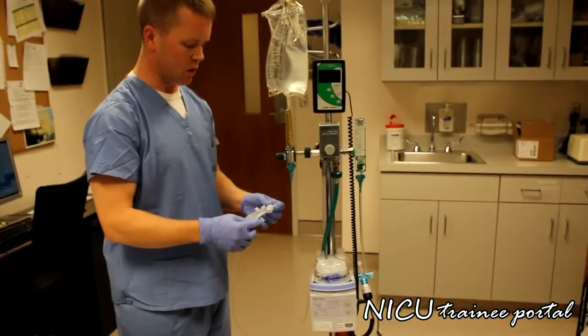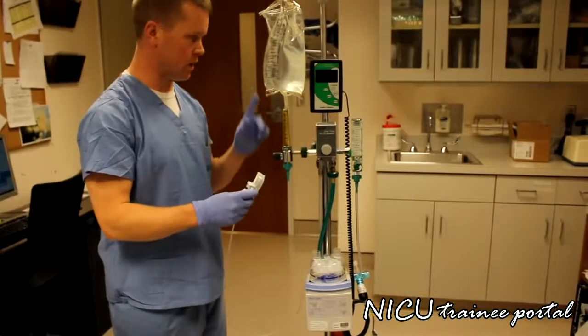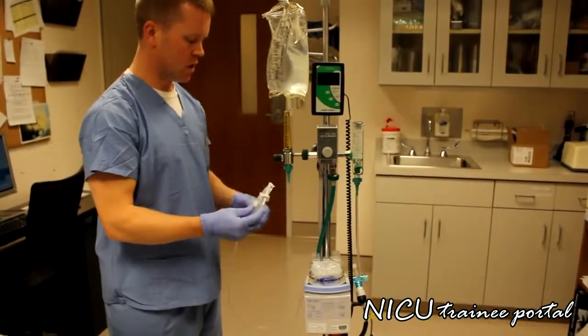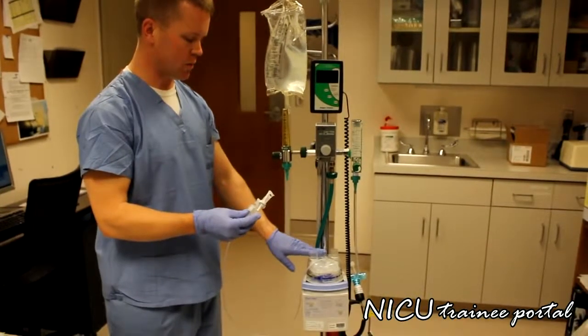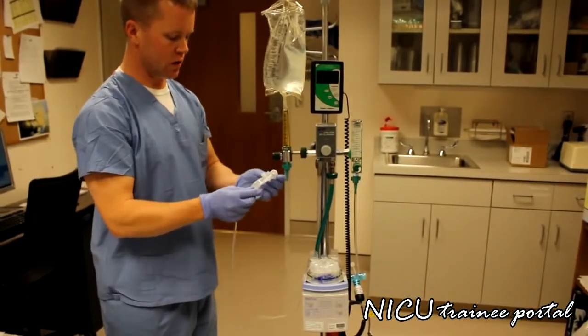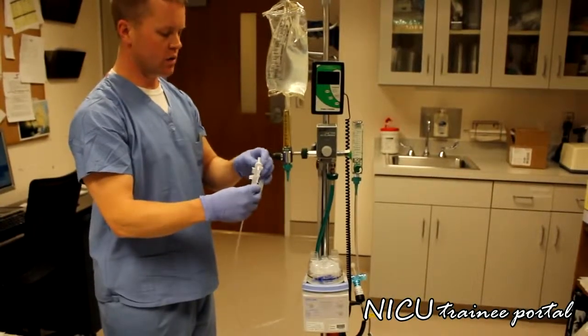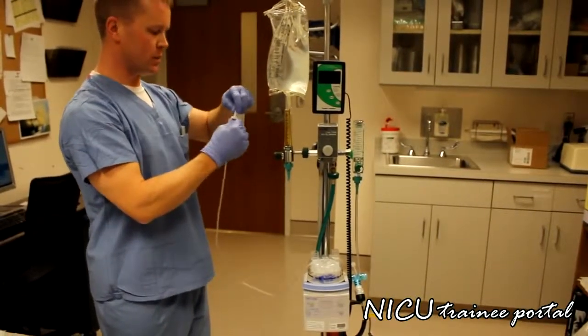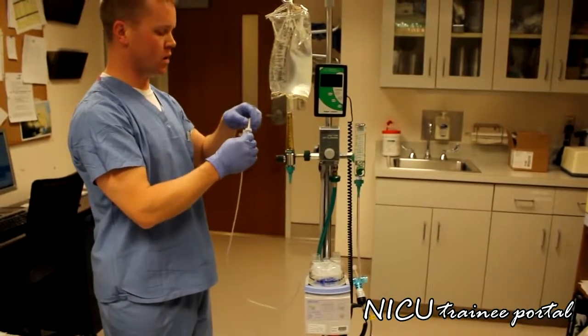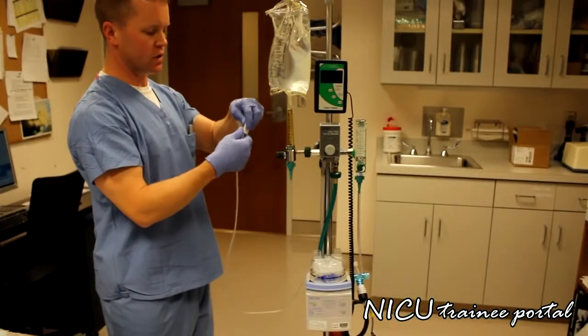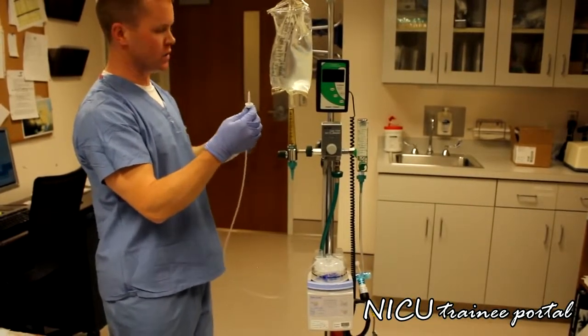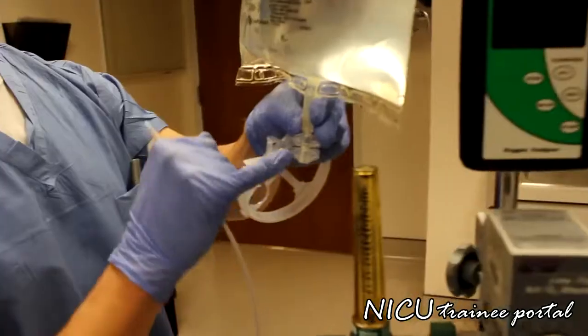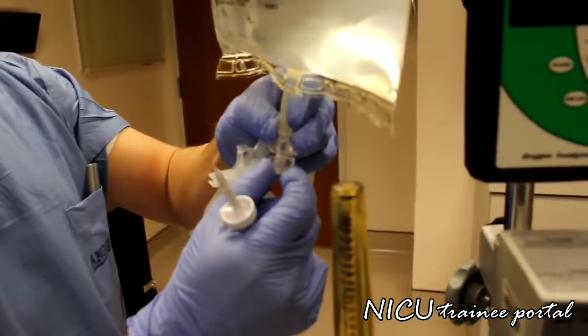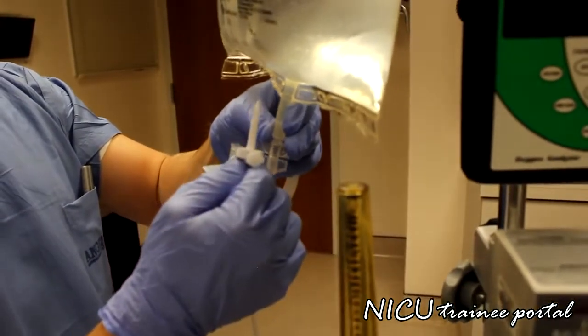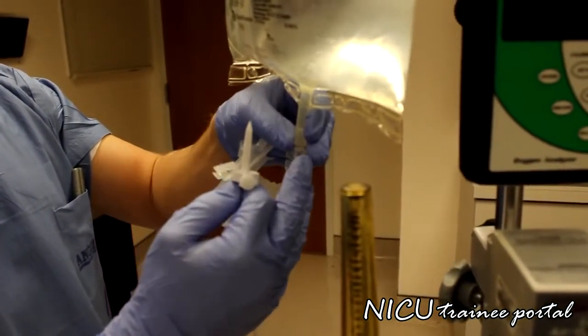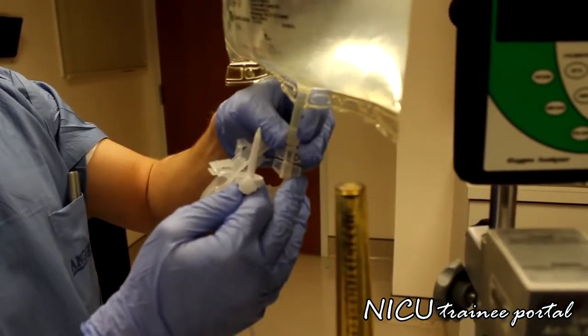Okay, the next component we will connect is the water line to the sterile bag of water for inhalation purposes. Attached to the heater to the water chamber is this water line. So it comes raveled around this piece right here. You unravel it, and for demonstration purposes, we will not be spiking this bag of water, but inside of this little plastic connection is a spike. And when you're ready to, you displace plastic on the bottom. This piece twists off. You take your spike, you spike the bag of water, and then you will see the water draining into the water chamber.